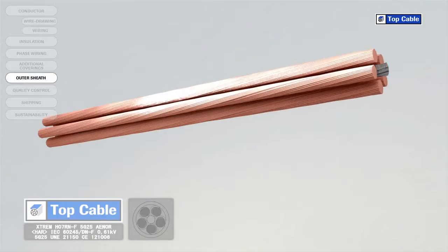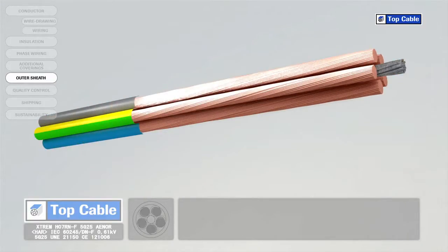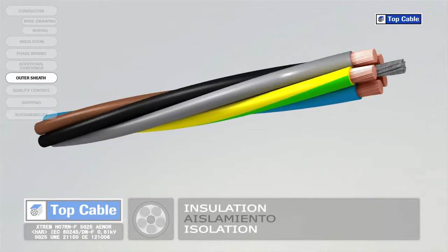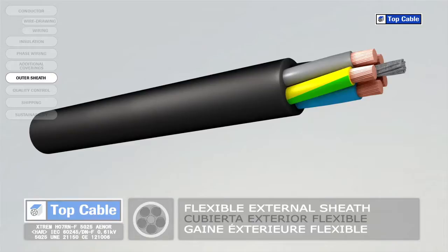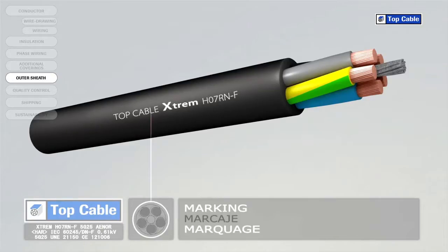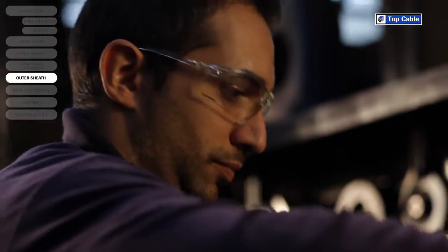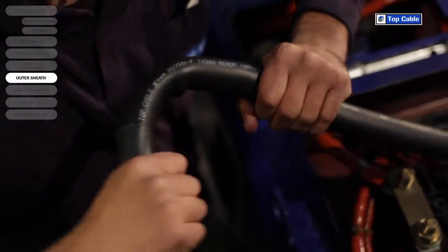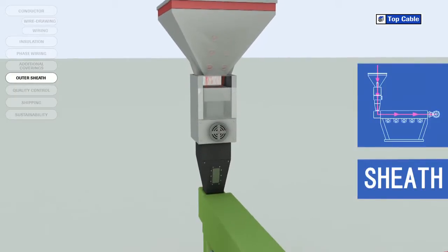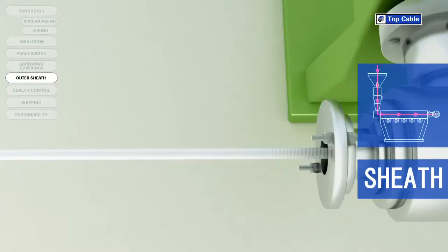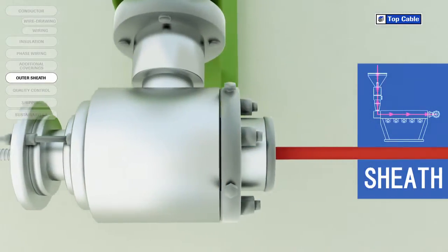Cables usually have an outer polymer covering for protection, called the outer sheath. The sheath protects the conductors and their insulation from external elements which may change their electrical properties, such as moisture. It also protects them from mechanical aggression which may occur during the installation of the cable. As with the insulation, the outer sheath can be made from a thermoplastic or a thermosetting plastic, and is applied via a process of extrusion at high temperature. The material chosen depends on the required protection level, the final flexibility of the cable, and the work environment.